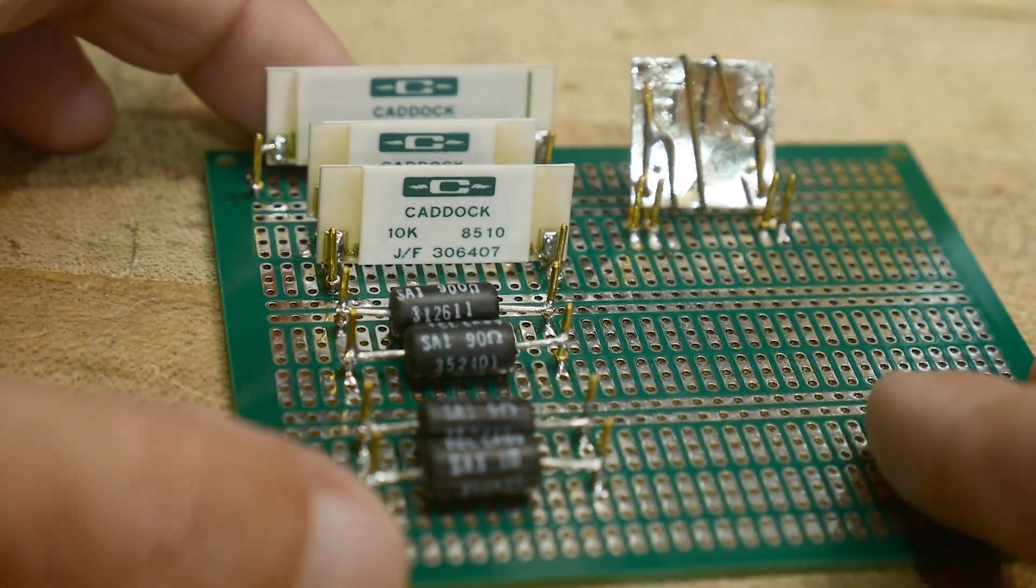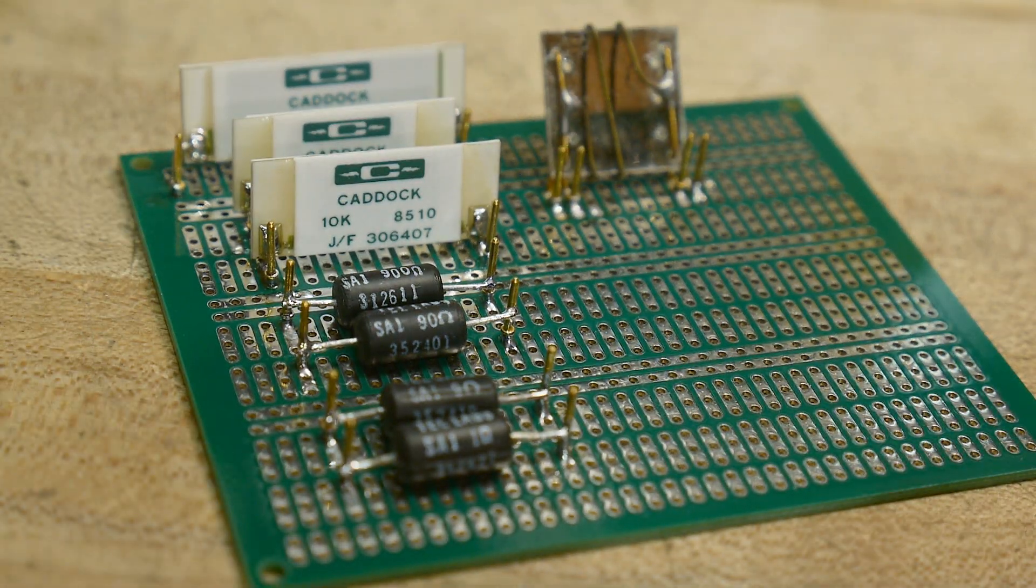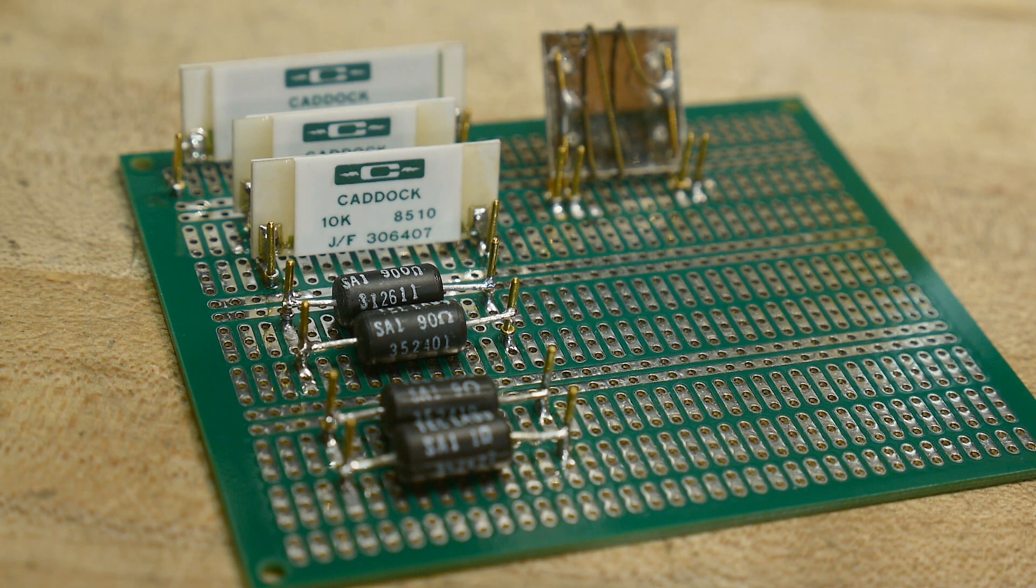I saved some really nice resistors. In the old DVMs they weren't software calibrated, they were hardware calibrated. Calibrating for every single range would have been expensive, so what they did was they calibrated for one range and then they multiply that up for all other ranges.